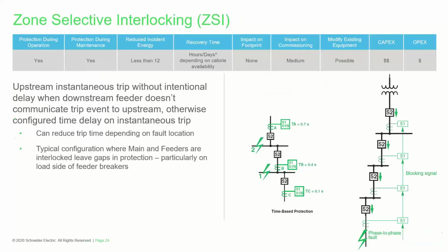And so for some of the specific solutions, I've picked a few of the popular reduction solutions to look at. One example here is zone selective interlocking, just to give you an idea of the guidance shown. ZSI, of course, is a system where you have communications wiring between different levels of protected devices, either circuit breaker trip units or protective relays. The idea is that if a device is not seeing a restraint signal from something downstream, you trip very quickly, with no intentional delay, instantaneously, however you want to put it. And that could help you reduce clearing time in some instances.